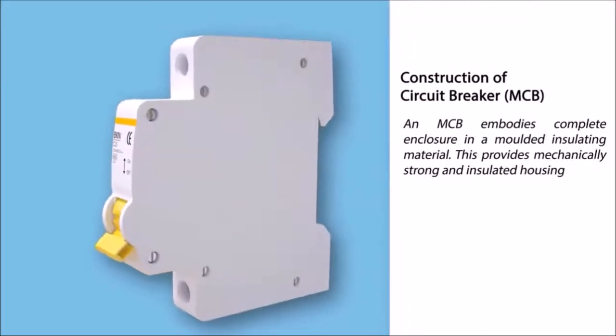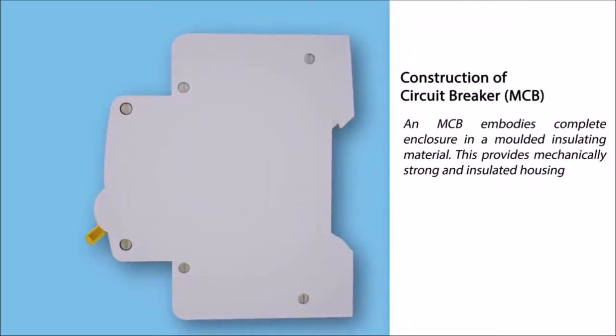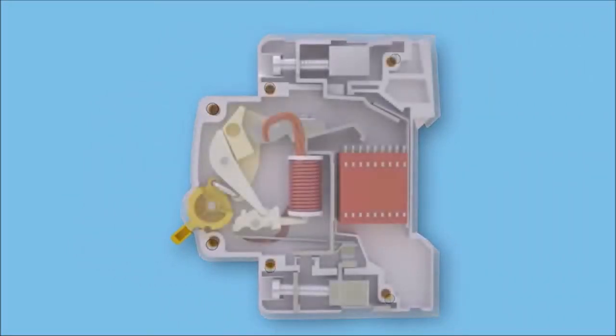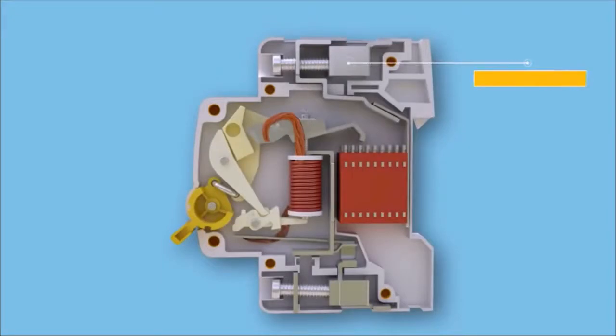Construction of circuit breaker, MCB. An MCB embodies complete enclosure in a molded insulating material. This provides a mechanically strong and insulated housing. Remaining parts of MCB are: incoming terminal. Incoming terminal is made up of electrolytic copper or silver alloy, and this is where the incoming phase is fixed. Next part is arc chute. Arc chute is a stack of mutually insulated parallel metal plates which divide and cool the arc.